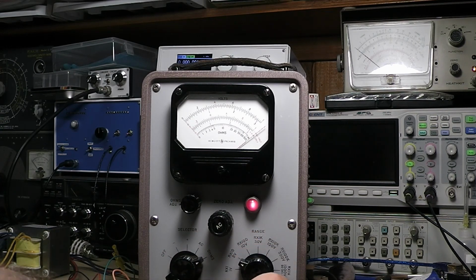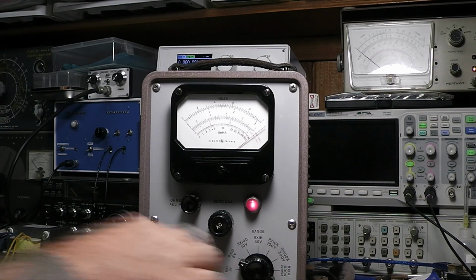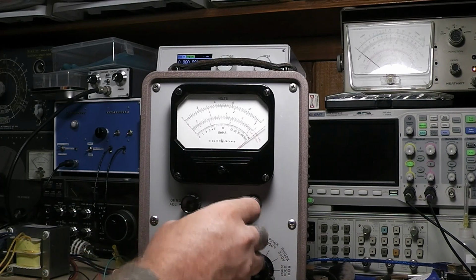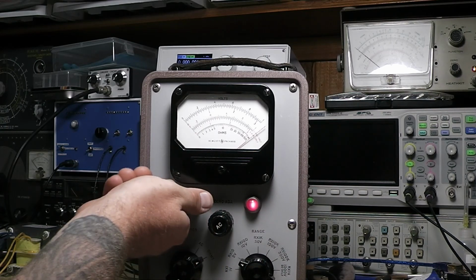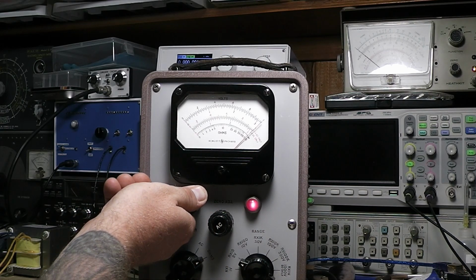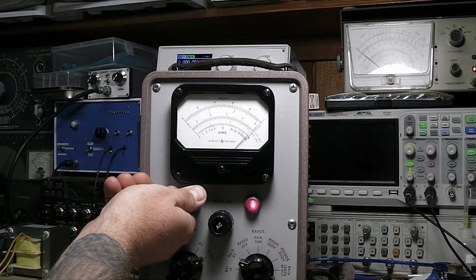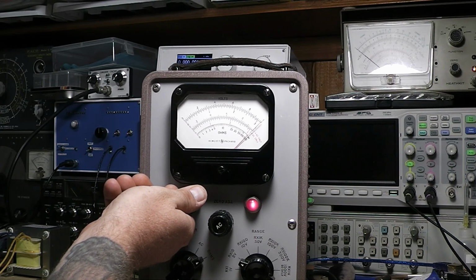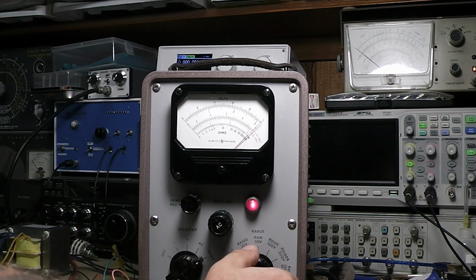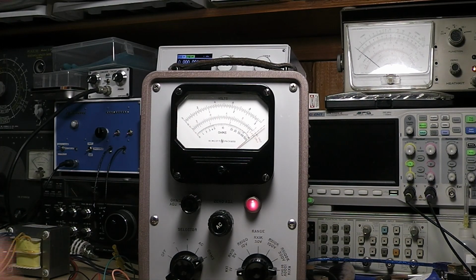what it says to do is put it in the RX times 10, and we're over on ohms. And you go for your infinity set here. Put that right on. Okay. And then go down to RX times 1. And if that don't match, then you got to adjust in the back. Now remember, that's where I took the selenium rectifier out and put those diodes in, so that's going to affect things.